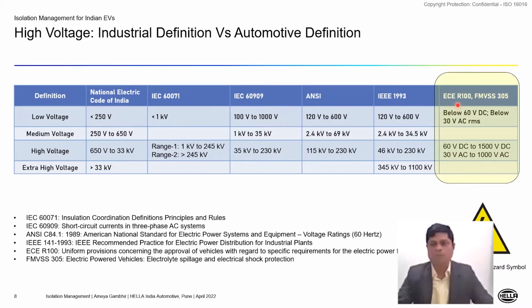The definition is derived from the UN standard ECE R100, which is also available in the US standard FMVSS 305. In our industry, anything below 60 volt DC or below 30 volt AC RMS is considered low voltage. Anything between 60 volt DC to 1500 volt DC, or 30 volt AC to 1000 volt AC RMS, is considered high voltage.